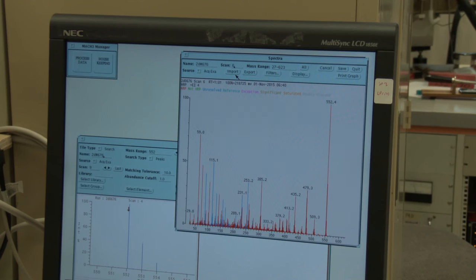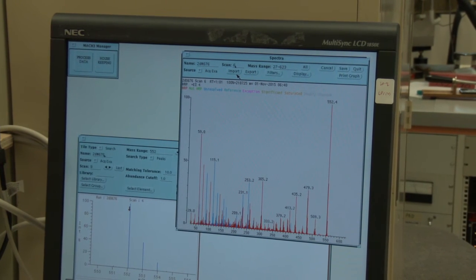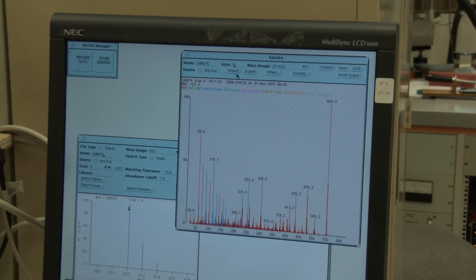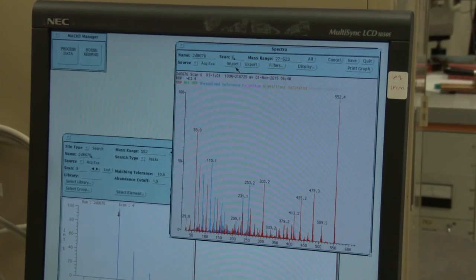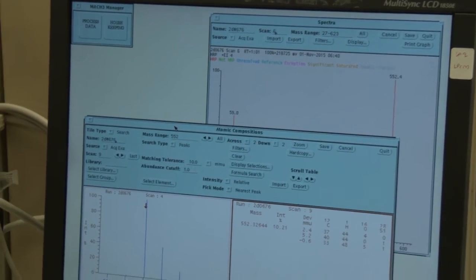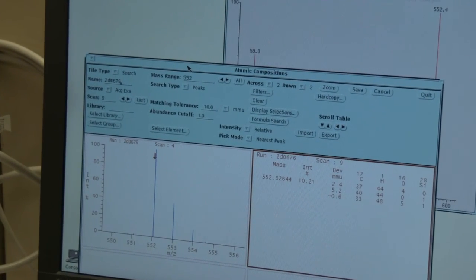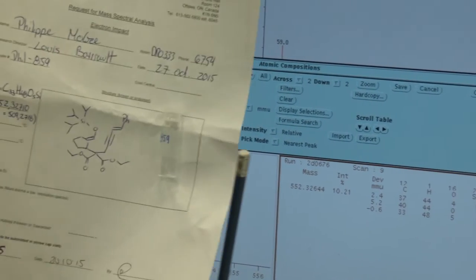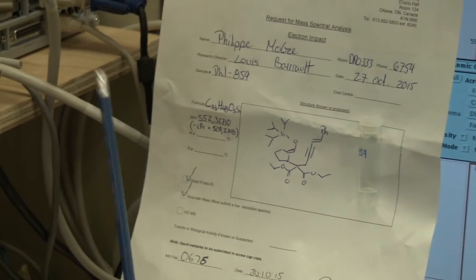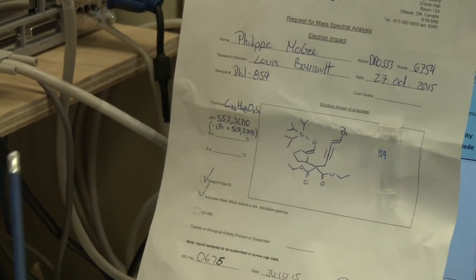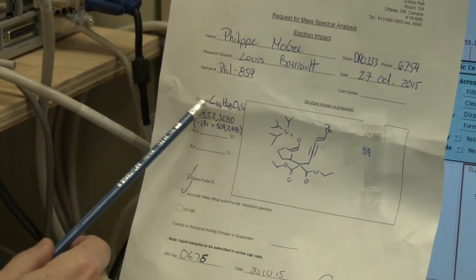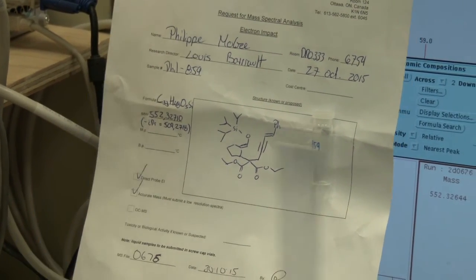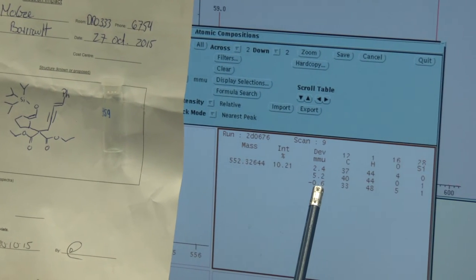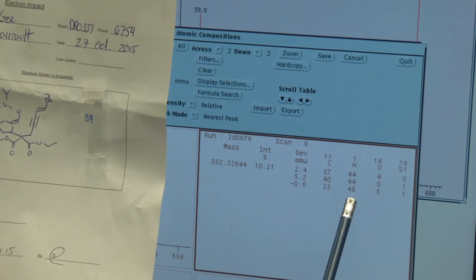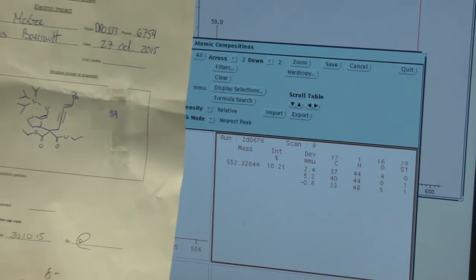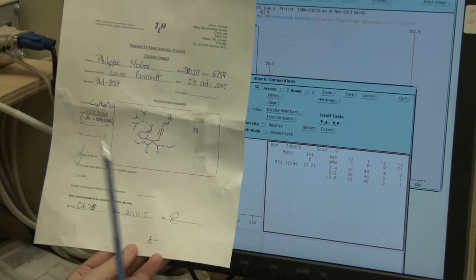Bingo! Because of the calibrant and the mass resolution of the Concept, we are able to use the instrument software to determine what molecular formulas are within a few millimass units of this molecular weight. If Philip's expected formula is within 5 millimass units, it can be stated with confidence that he has that particular compound. These results can then be published. The instrument has found 3 possible formulas that add up to that mass, and the bottom one is Philip's molecule, and it is within 0.6 millimass units from the expected mass, which makes it publishable. Well done, Philip.